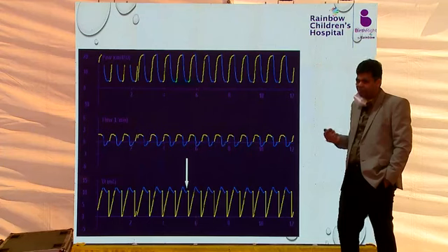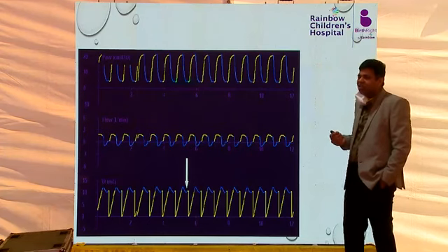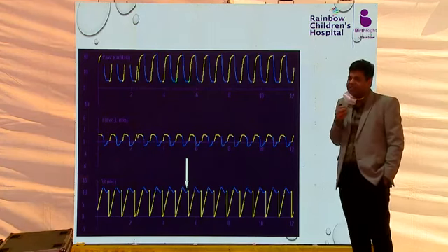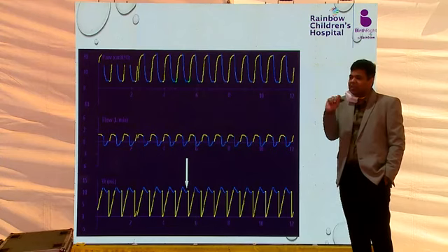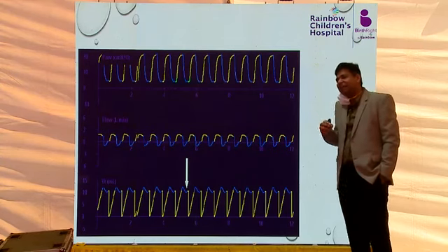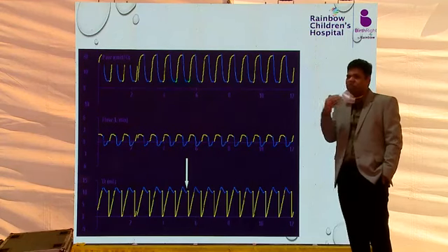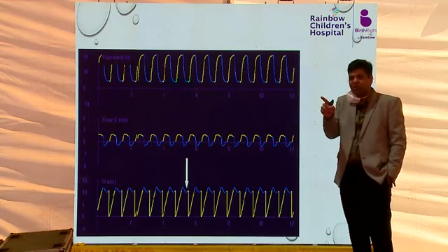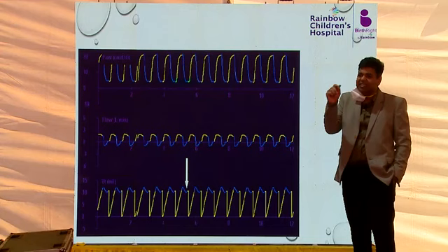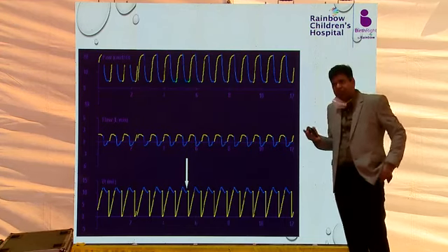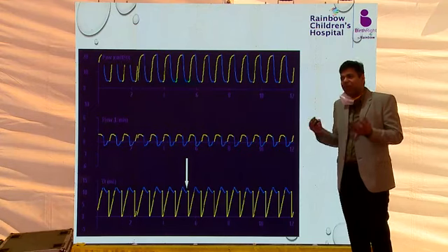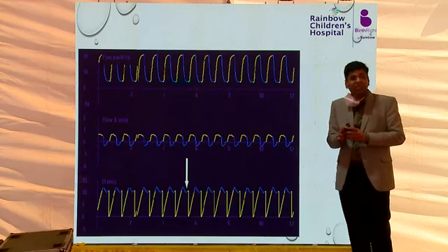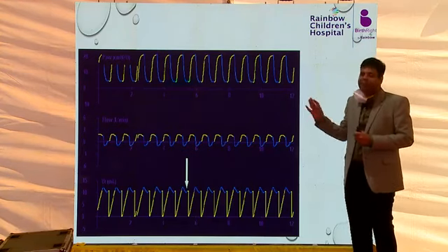Have you heard about autocycling? So autocycling is, if there is water in the circuit or if there is a peritubal leak, what happens is the flow sensor will judge these changes in the flow as a breath initiated by the baby. If there is too much water in the inspiratory circuit, the same thing is going on. Although it's a single inspiration, the flow sensor may calculate it as first breath, second breath. And in synchronized modes like SIPPV or pressure support, where all the breaths initiated by the baby are synchronized and fully assisted by the machine, the machine starts assisting every breath.